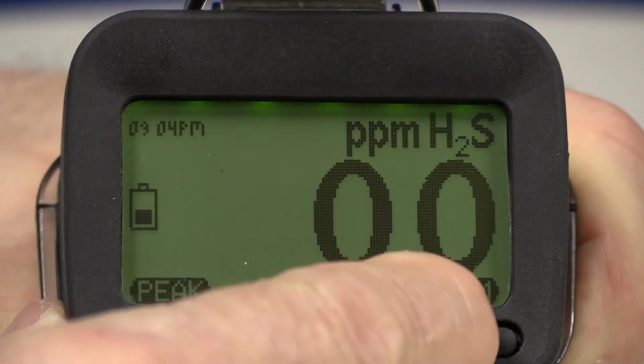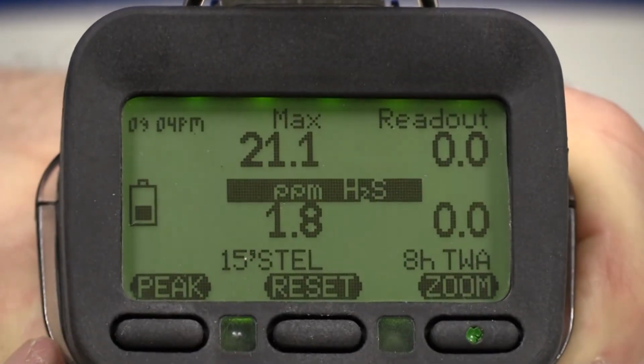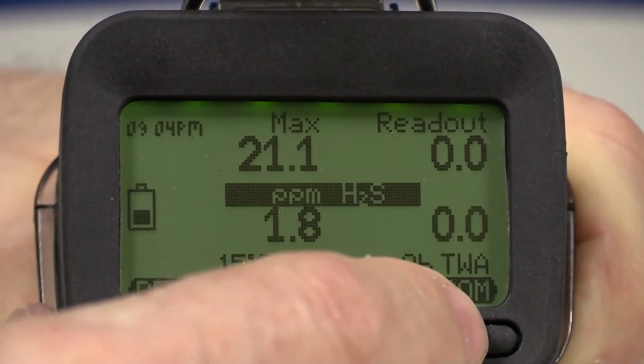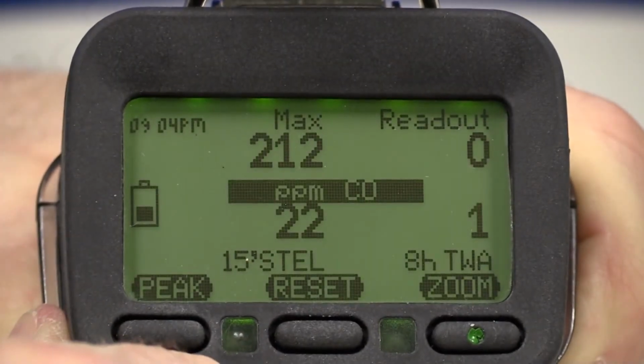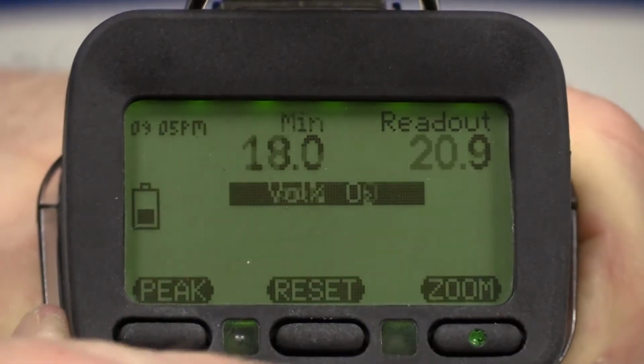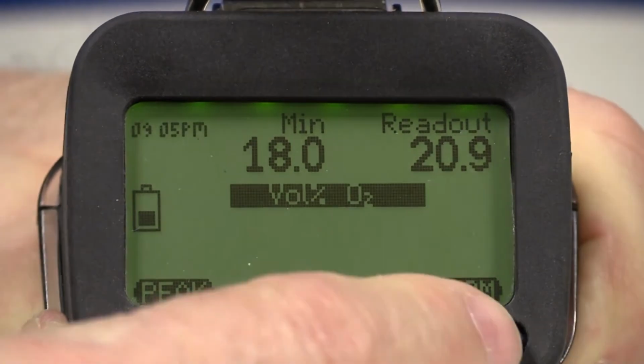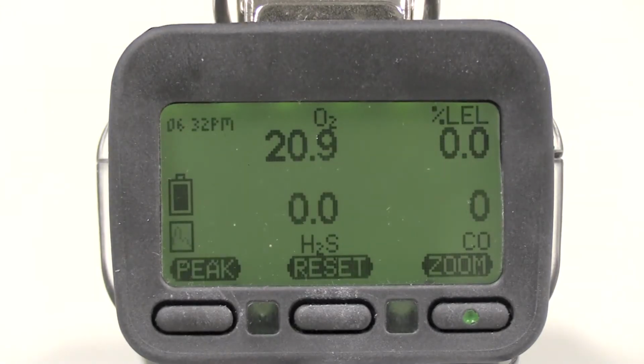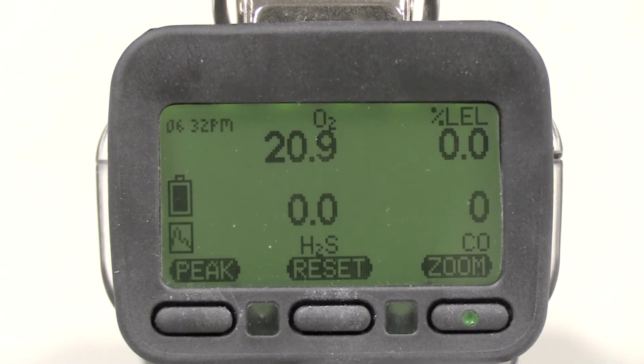If you press and hold down the zoom button while the numbers are large, you can see the peak readings for each sensor as well as the STEL and TWA calculations for the CO and H2S sensors. In normal operation, the instrument displays a separate reading for each sensor. The units used for the measurement depend on the sensor.